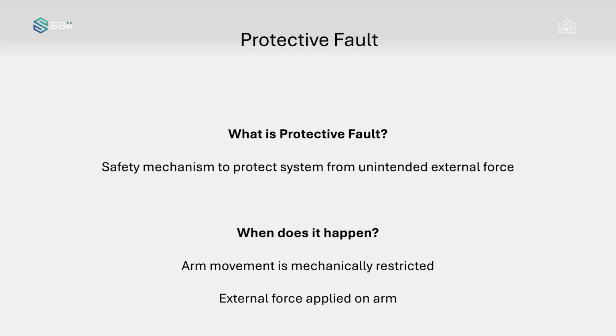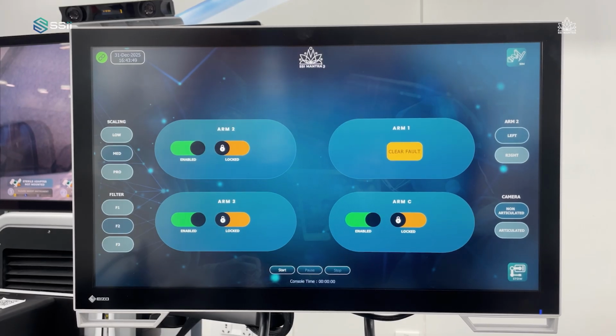Protective fault is a safety mechanism designed to address operational deviations while the surgeon is controlling the arm using the hand controllers. Protective fault may occur when the arm movement is mechanically restricted or any external force is applied on the arm while the arm is being operated with the hand controller by the surgeon. Only the affected arm is impacted with protective fault, the rest of the system remains operational. Indication: automatic disabling of the affected arm.